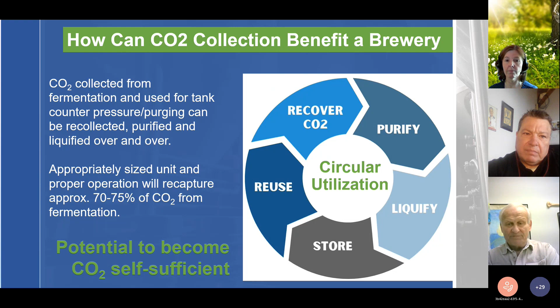How much CO2 is generated for fermentation? It's pretty simple: if you have less sugar, you're going to have less CO2. Sugar refers basically to the gravity of the brewing you're doing. Generally speaking, if you want higher alcohol, you put in more sugar extract, what we call fermentable sugars. So less sugar, less CO2, more sugar, more CO2. As a rule of thumb, for rough design and talking numbers, 8 to 10 pounds of CO2 per barrel is usually generated. We use 9 pounds as a good talking number. That'll change again based on how much fermentable sugar is in your wort.